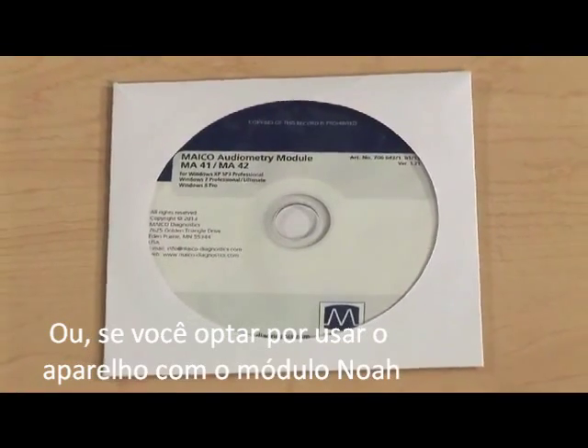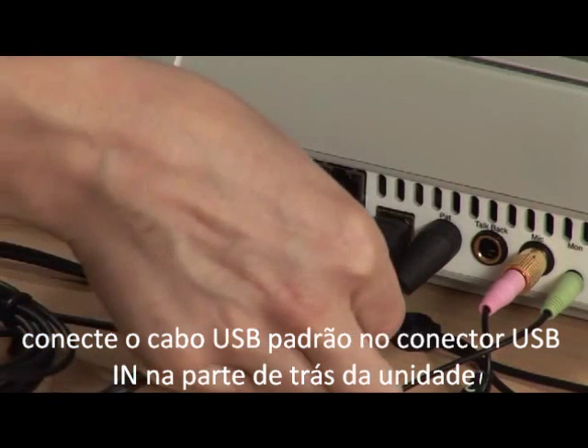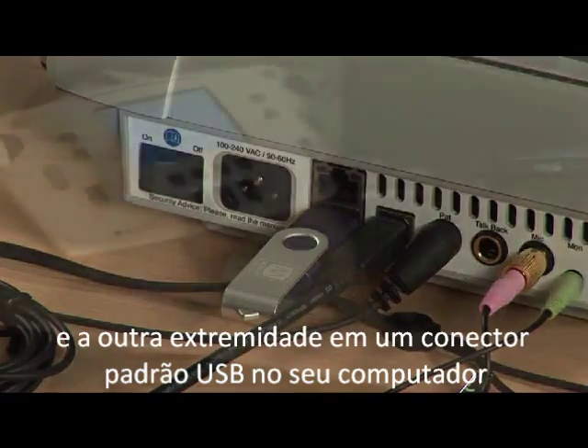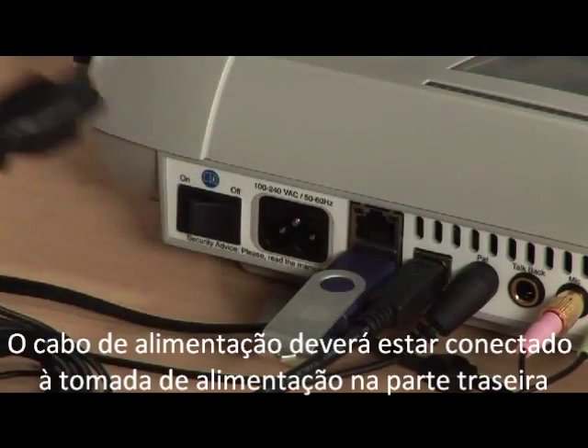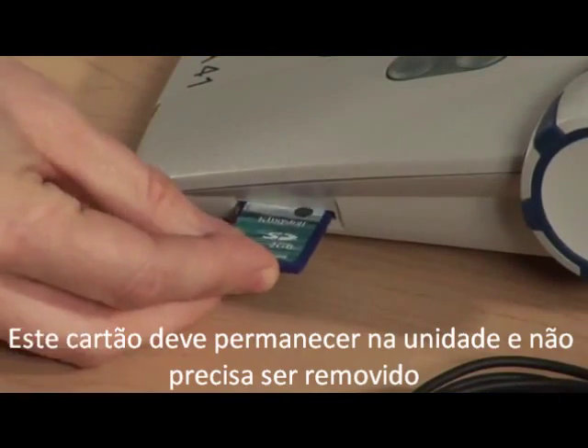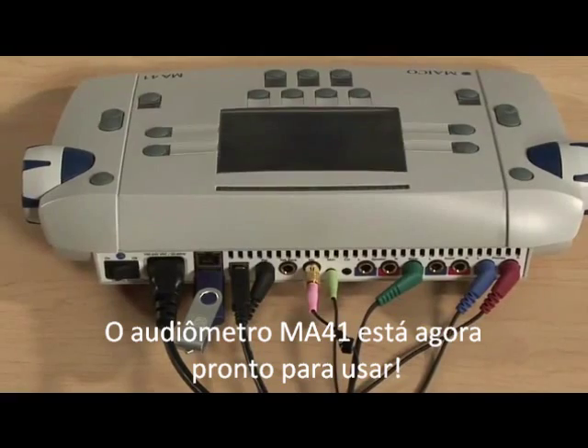If you choose to use the unit with the Noah module, plug in the standard USB cord into the USB in slot on the back of the unit and the other end into a standard USB outlet on your computer. The power cord is plugged into the power outlet on the back. The SD card contains the WAV files for the unit and gets inserted into the slot on the right side of the unit. This card should stay in the unit and does not need to be removed. Your MA41 audiometer is now ready to use.